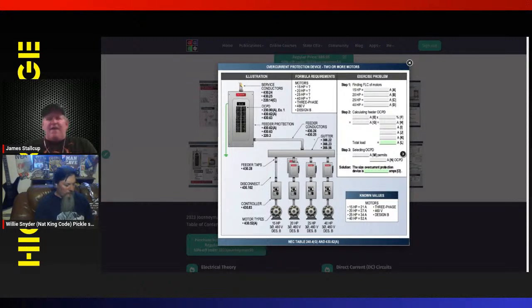I'm going to have in there: 240.4G will be your start, and basically that's going to take you to table 240.4G. It's going to tell you anytime you're sizing the overcurrent protection device, you're going to go down and look at your motors and motor control circuits, and look at all of these parts. Then the next section you're going to look at is 430.6A1, and it says anytime you're sizing your conductors or overcurrent devices, to look at tables 430.247 through 250.